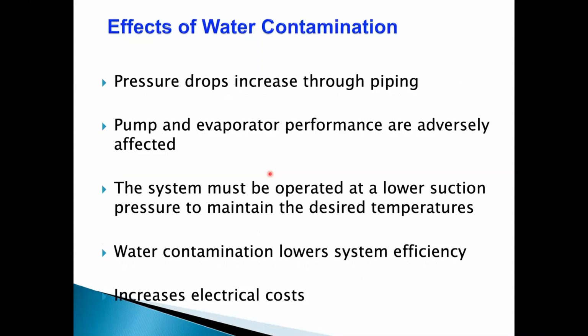Because of the water sludge in the ammonia, the pressure drop across the pipe increases. The pump and the evaporators are adversely affected, because remember, air accumulates on the high pressure side because it is lighter than ammonia, whereas water accumulates on the low pressure side because the partial pressure of water is much lower than the pressure of ammonia. And we have to operate at a lower suction pressure. You need more capacity, so it increases cost.